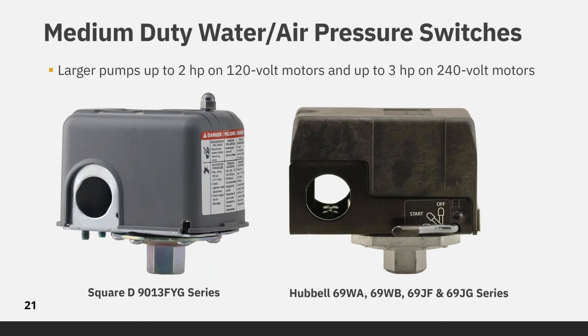Medium duty pressure switches are best used with larger pumps up to 2 horsepower on 120 volt motors and up to 3 horsepower on 240 volt motors. Hubbell's 69J series is the most adaptable switch on the market. It offers the user the flexibility to build the pressure switch around the compressor and not the other way around. The unloader can be mounted on either side and can be rotated to any of eight different positions, allowing for quicker assembly and shorter tubing.